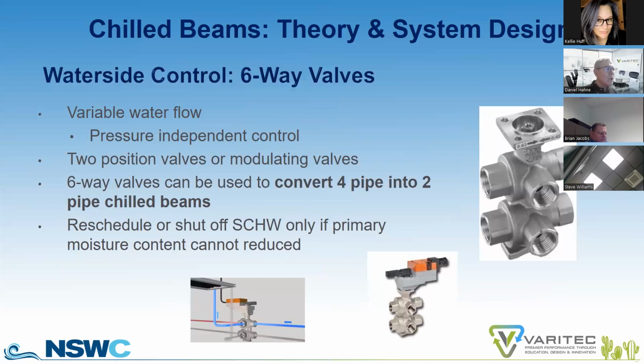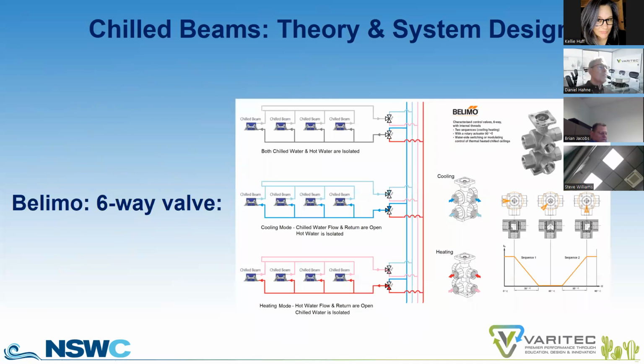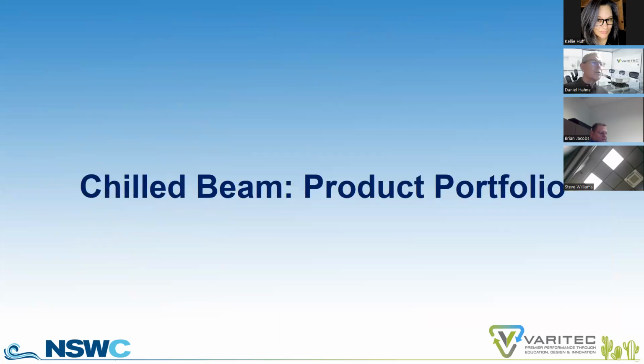To reduce the cost of valves, so we don't need a hot water valve and a chill water valve, Belimo has an excellent technology of a 6-way valve with a common actuator that should be evaluated to reduce first costs. And this just gives you a piping schematic on how a 6-way valve might be used to actually save on that water flow control solution.